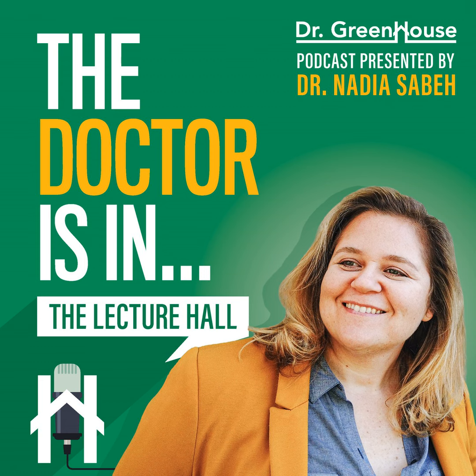And the other thing is that it can give you a sense of what sensors are useful and what sensors maybe we don't need. So, you see this image behind me and there are actually a few more sensors off screen that you can't see in this photograph. And it was mind-boggling because every single sensor that we use to monitor temperature had a completely different readout. It could have been plus or minus half a degree, but we saw plus or minus 3 or 4 degrees.